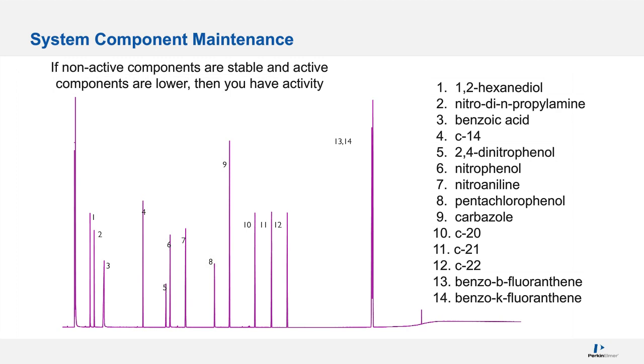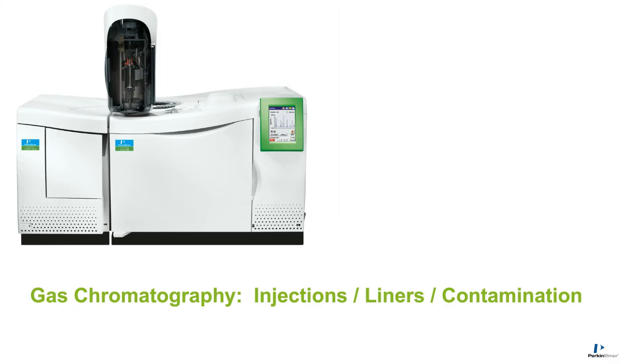I find the liner is most of the problem. One time I was having a problem and I took out my liner. It looked perfect, but I changed it and my problem went away. So just inspecting the liner doesn't mean that it doesn't have something on it that's not visible to us, especially if it has a scratch in it, because a scratch exposes the glass that was not deactivated. So even a little scratch can cause an activity problem.